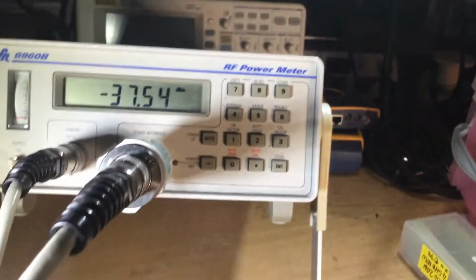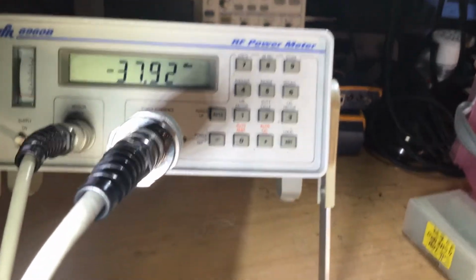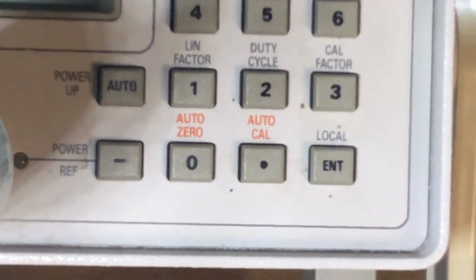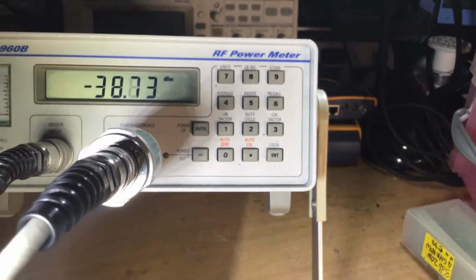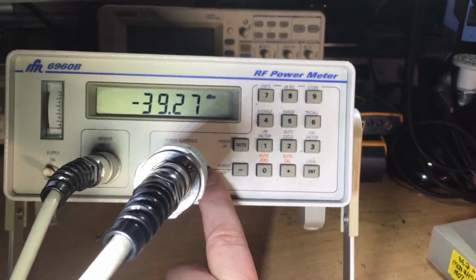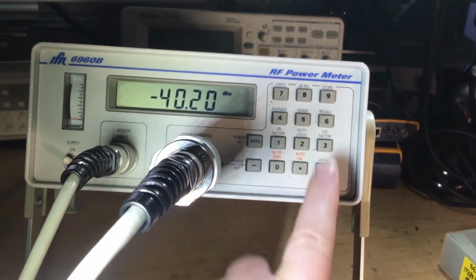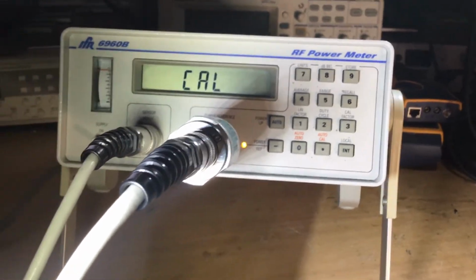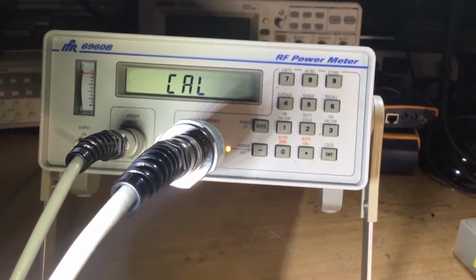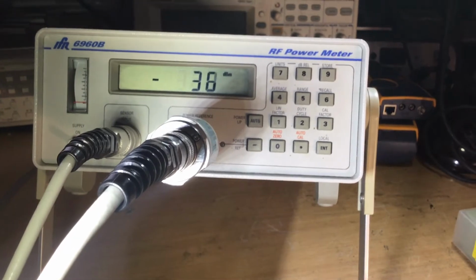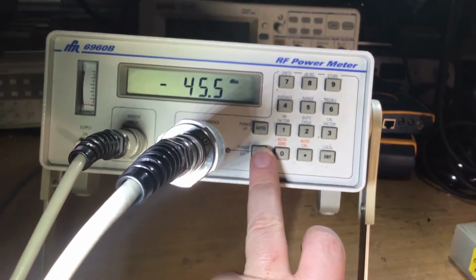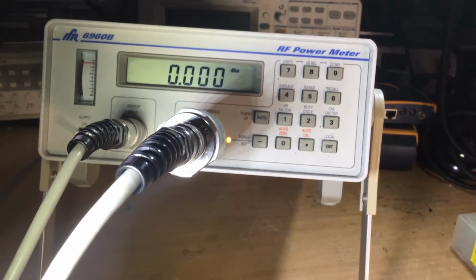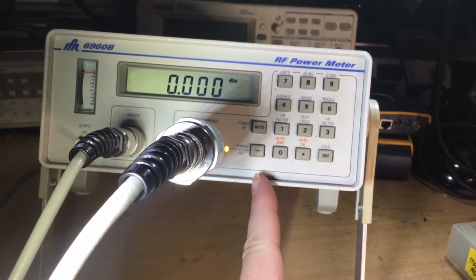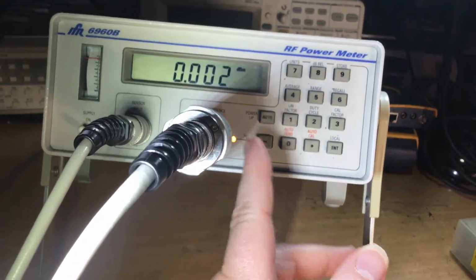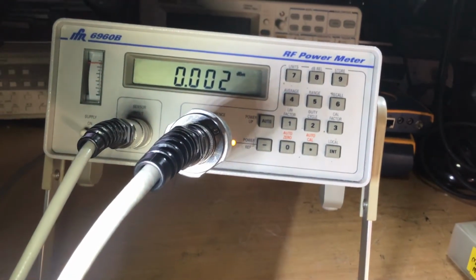Right, so we've got here just down in this section an auto 0 and auto cal. So we'll go for the auto cal. What that will do, it will put the reference on and then calibrate this against it. So that's what we'll do now. And it's just starting the calibration sequence. And then basically when we put the source on, it should read 0. So it's calibrated the internal reference against the power sensor being calibrated against the internal reference.